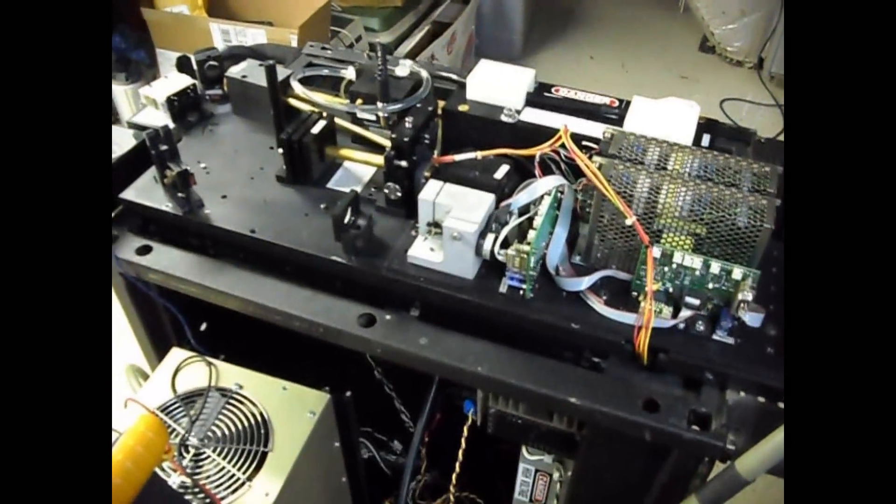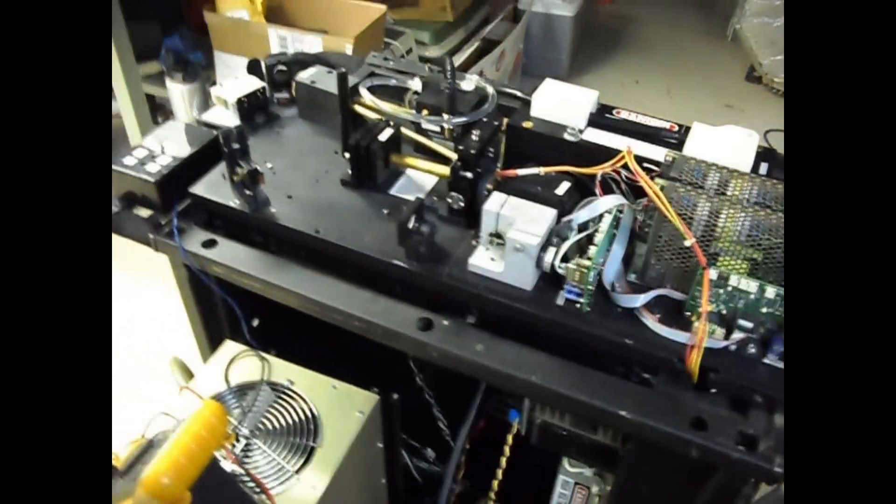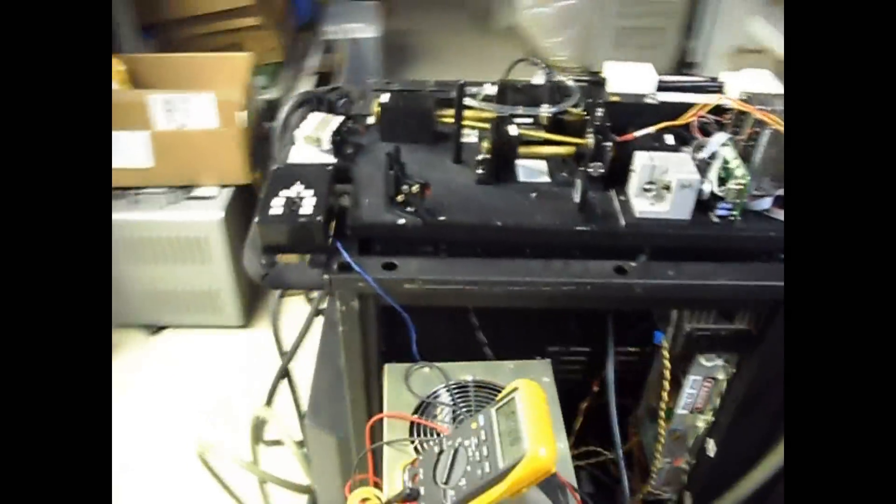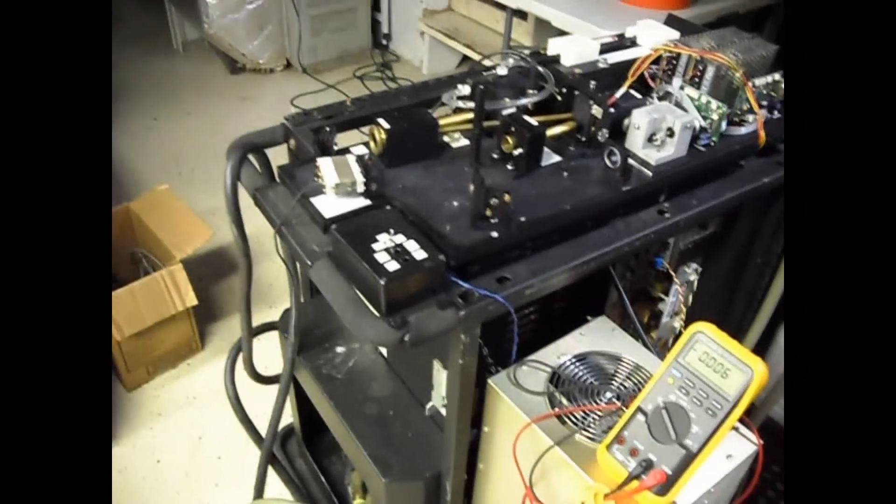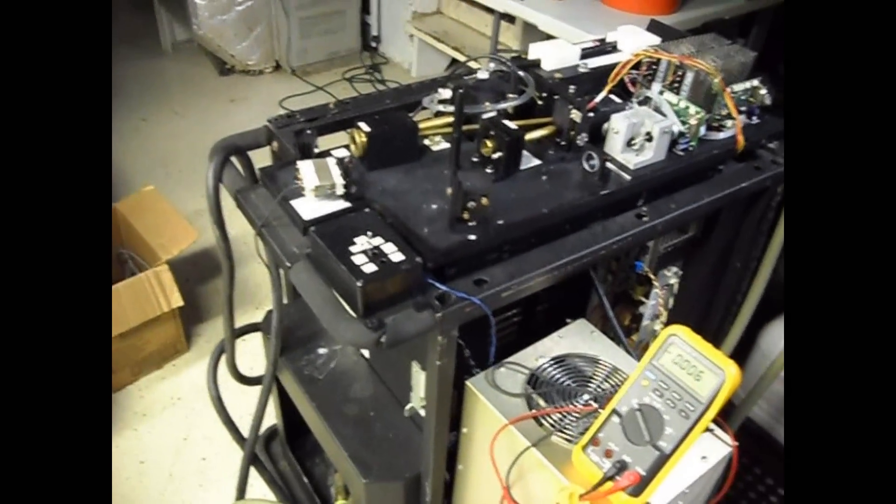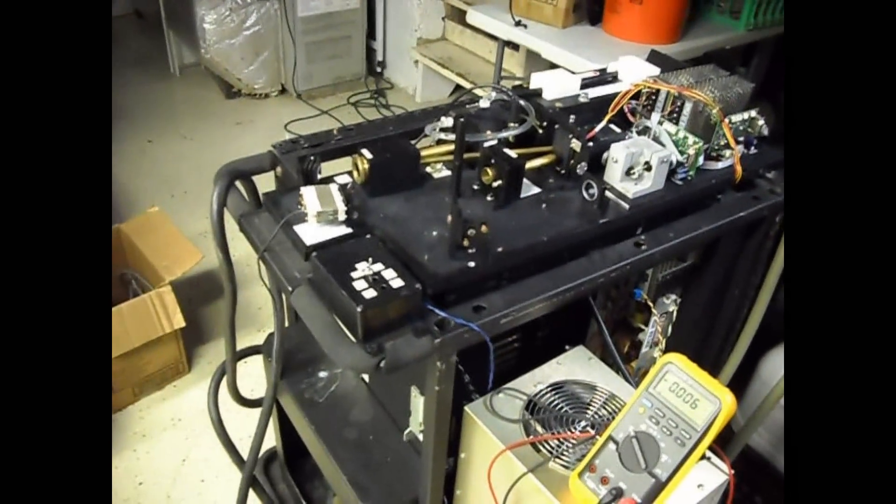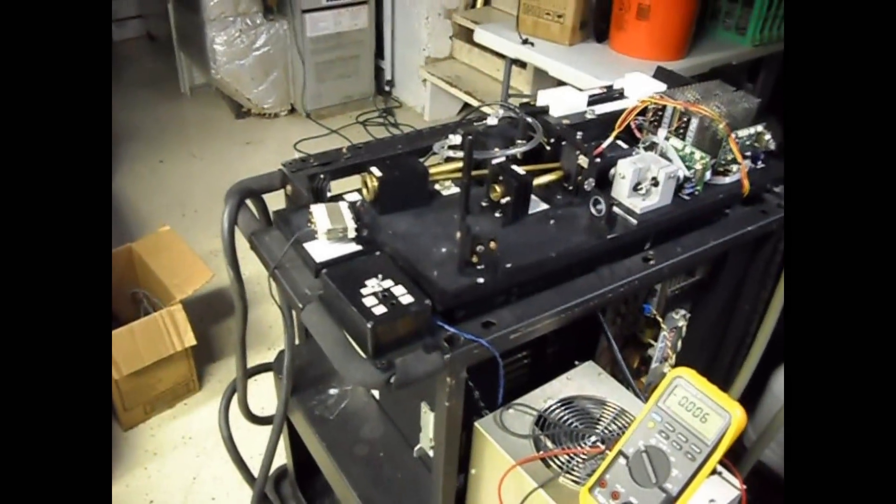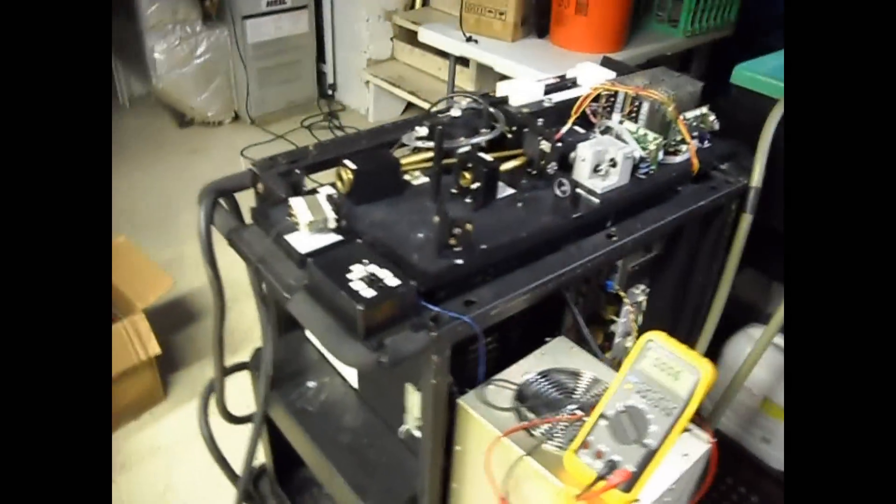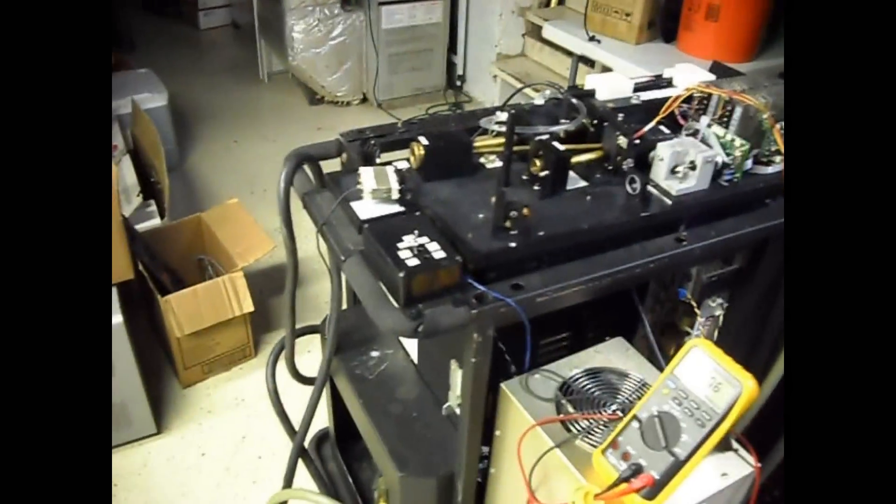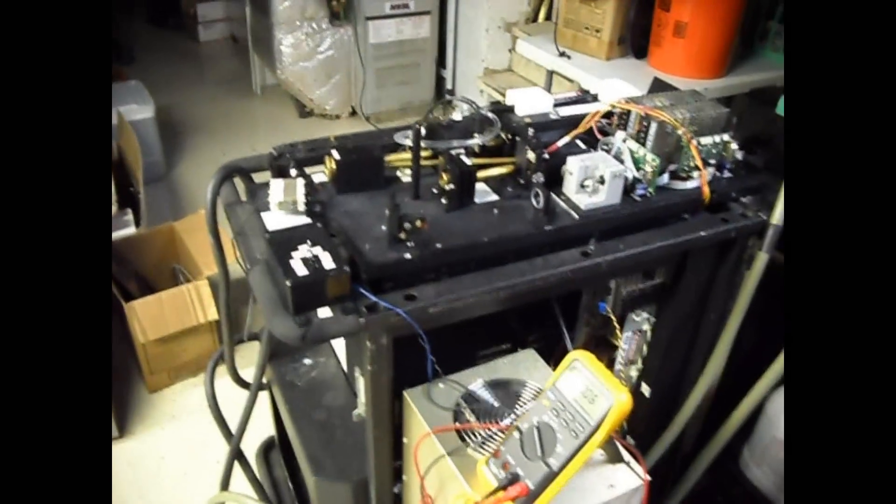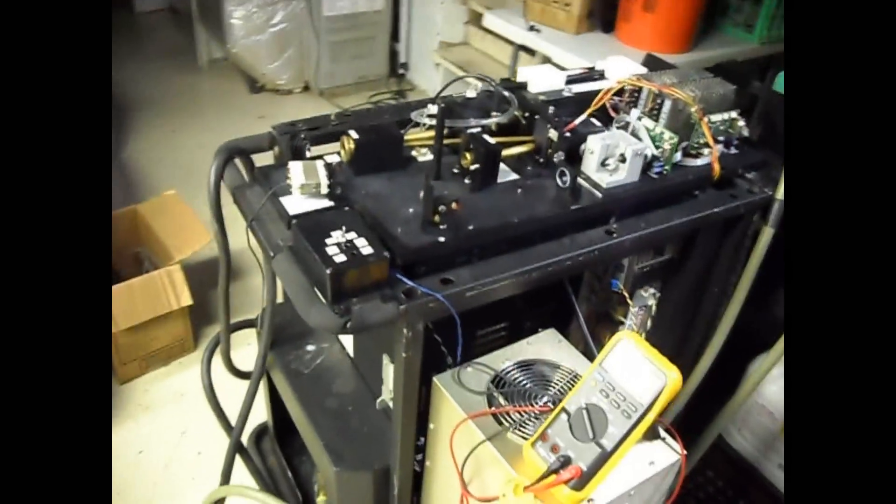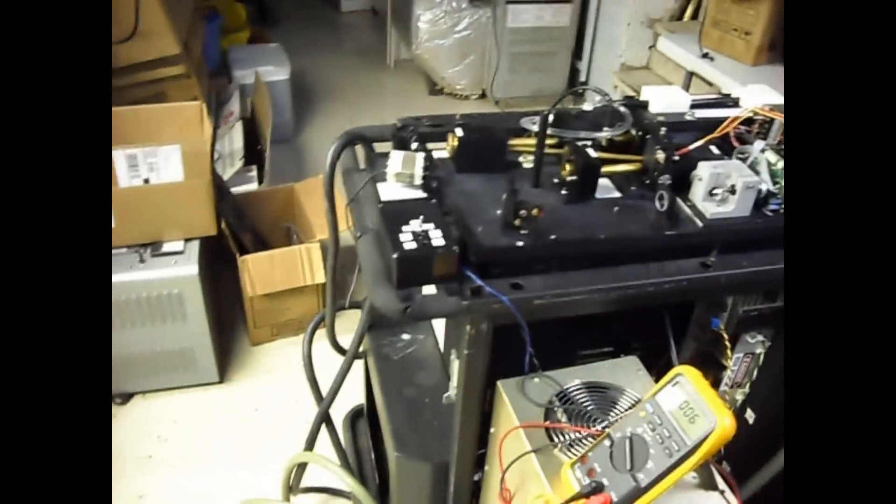So now we got that going, I'm going to go ahead and turn on some water here. This right here will keep the open loop with the side cool. One thing I like about this laser versus the ion lasers I'm used to working with is it actually throttles the water. You actually want to keep the closed loop operating of the coolant a little bit on the warm side for stability. So it actually starts off at a nice slow trickle and then starts going faster as the laser starts creating enormous amounts of heat.